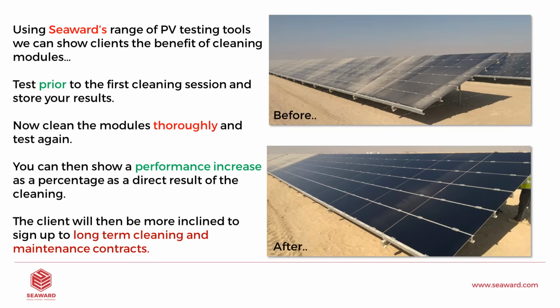Whenever you're testing, it's a good idea to take pictures, to note what the conditions were, and add this to your test results. It's no good just giving the client a bunch of numbers; we need to give context to those numbers. The good thing about our instruments is that if you can do a test before you clean, then clean the modules thoroughly, and then test again, we can show the performance increase to the client in real terms. This means we can set ourselves up for a real long-term cleaning and maintenance contract.